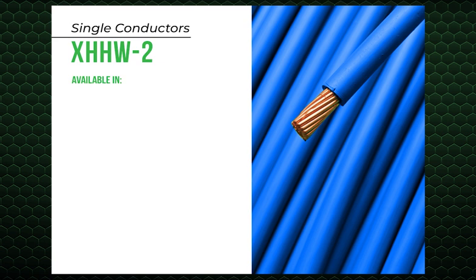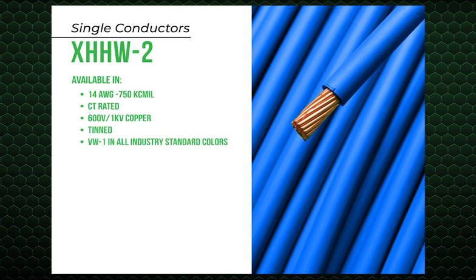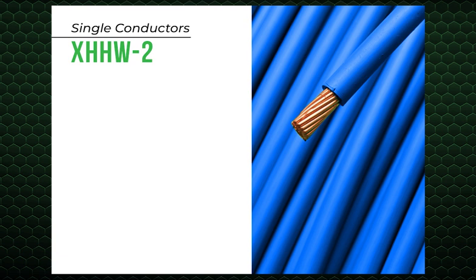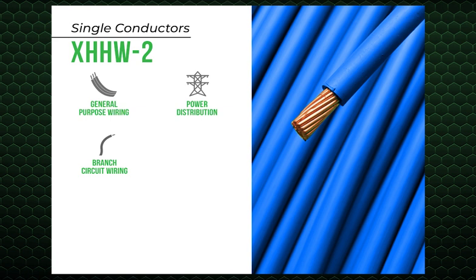XHHW is available in 14 gauge through 750 kcmil, CT rated, 600 volt/1 kV copper, tinned, or VW1 in all industry standard colors. XHHW-2 is used in general purpose wiring, power distribution, branch circuit wiring, 105 degrees Celsius dry systems, and low leakage circuits requiring dielectric constant of 3.5 or less.